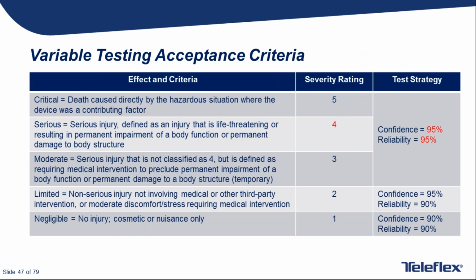Now, for the analysis after the testing, the 16 samples is completed. The acceptance criteria are that for a severity of 4, the required confidence level and reliability values are 95%. So in this case, with 95% confidence and reliability, the tensile strength of the needle should be greater than 22 newtons. And here we get into discussions about, is it best practice to have attribute and variable acceptance criteria the same? And the answer probably is yes.